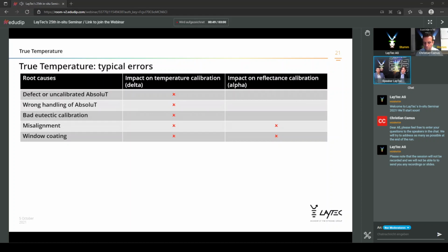even in case of damages. Broken or damaged parts within the entire viewport assembly can easily be detected by a significant sudden jump in the resulting alpha value. It's easy to imagine that if there's a severe coating on the window or anything else is impacting the transmissivity of the viewport, a subsequent alpha calibration will result in a very high alpha value. So it leaves the typical gradual development of the alpha curve and then shows a sudden jump.